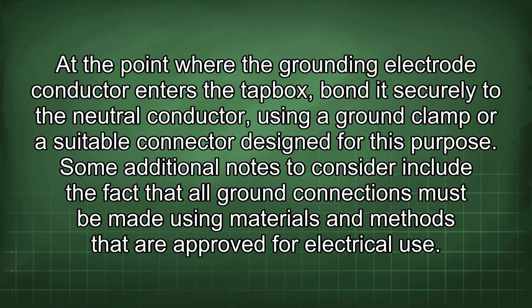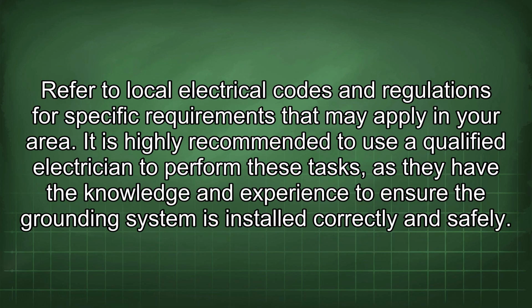Seventhly, the grounding electrode conductor must be bonded to the neutral conductor. At the point where the grounding electrode conductor enters the tap box, bond it securely to the neutral conductor using a ground clamp or a suitable connector designed for this purpose. Some additional notes to consider include the fact that all ground connections must be made using materials and methods that are approved for electrical use. Refer to local electrical codes and regulations for specific requirements that may apply in your area.